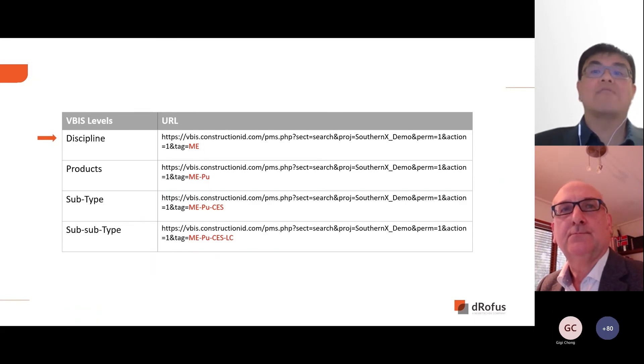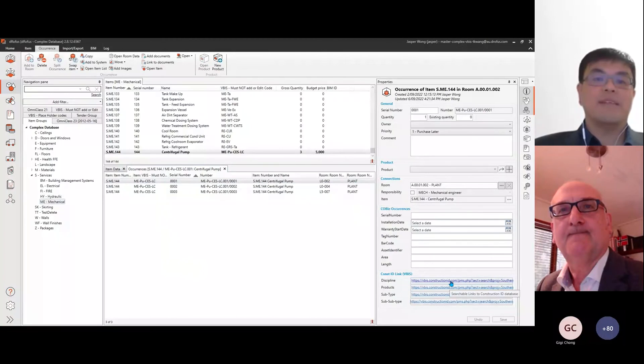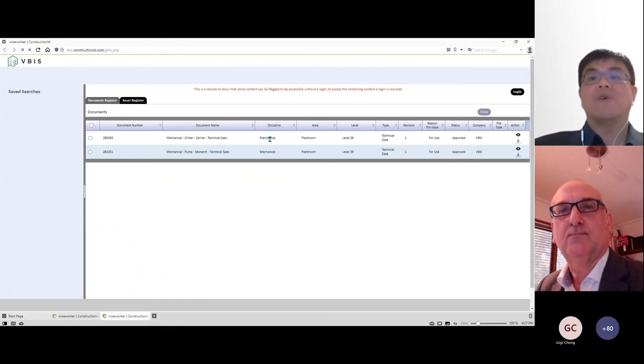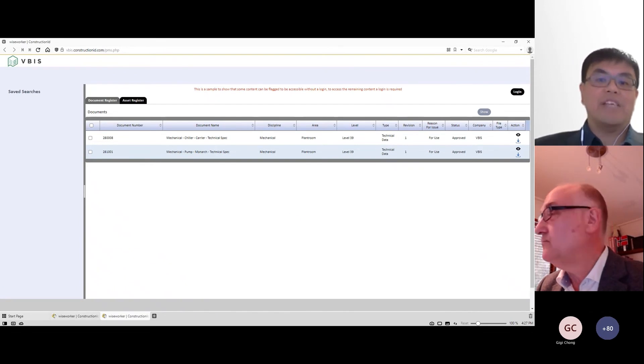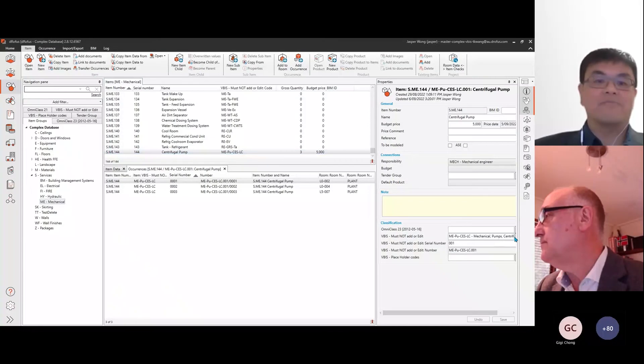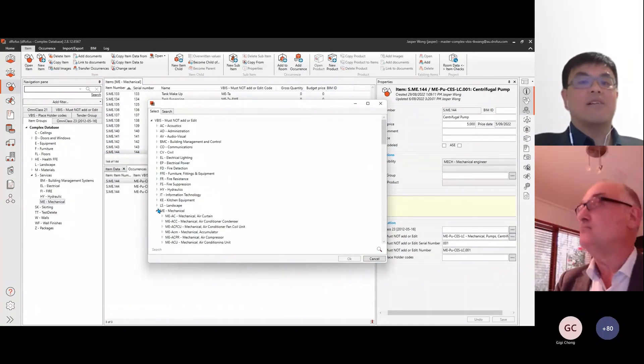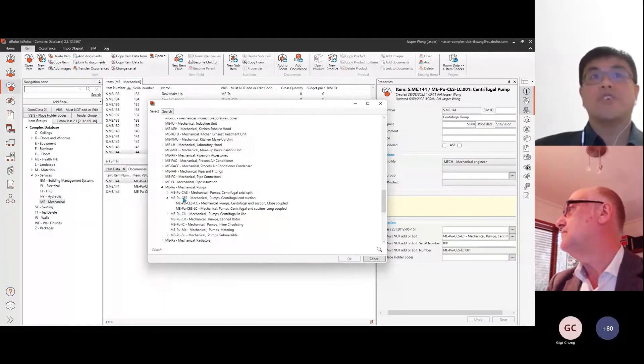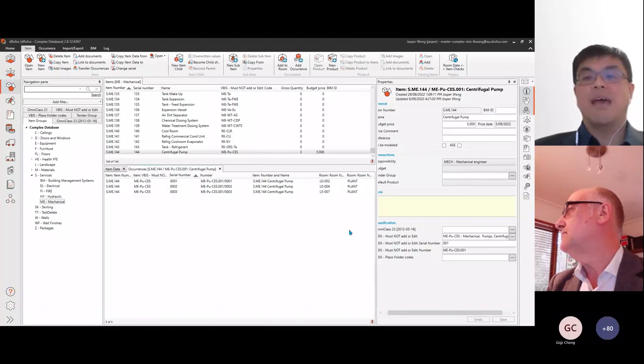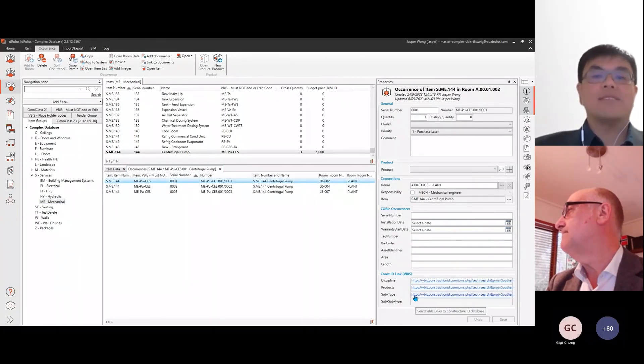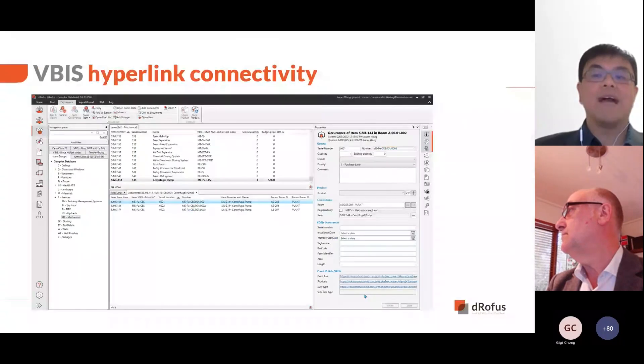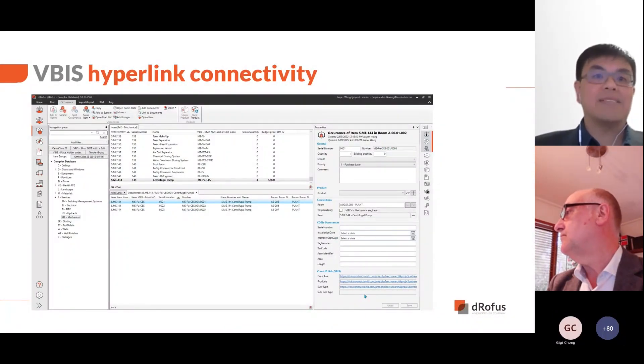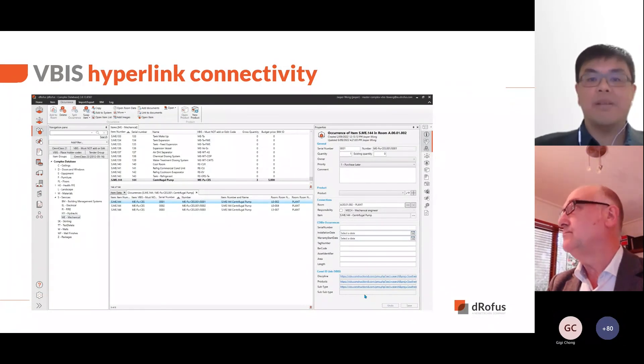Selecting a URL based on higher-level VBIS codes will present more information as there are more items grouped at that level. For example, when we select the discipline level URL, it will show all the equipment under the ME classification. You may ask: what happens to the URL if I assign only to the third level classification? In that case, dRofus will only show the URL up to the classification levels assigned. And here's a thought: if your project requires all elements to have a fourth-level VBIS code, you can display the fourth-level URL in the occurrence panel and quickly isolate elements that have a blank URL — indicating items without a fourth-level code — and update those quickly if required.